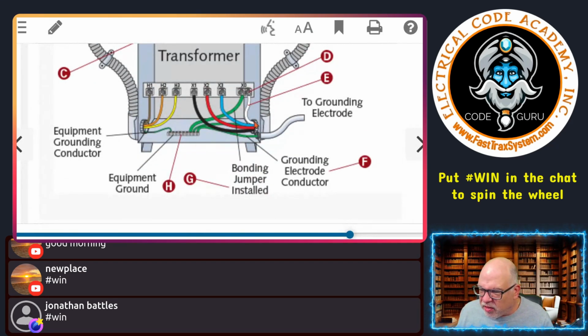So what you see here is all this connection, and here's your grounding electrode conductor coming over. All this is intimate, all tied together because of a properly sized system bonding jumper. This grounding electrode conductor is going out to, let's say, the electrodes, or it could be going to the water pipe system if you meet its rules, or out to the building steel, like the I-beams and inner framing, all under those caveats in 250.68. But it is sized based on the derived conductors, and that's these, and you go to 250.66 to size it. Make sense?